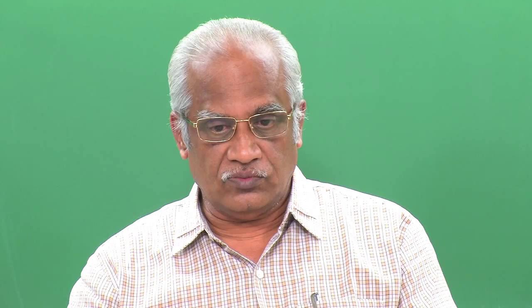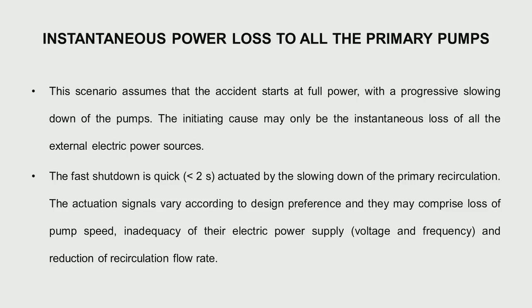Another scenario: there is an instantaneous power loss to all primary pumps. The primary pumps receive no power. They have some inertia in their drive system, so they slow down gradually, but the power is gone. This is an unsafe situation, so we trip the reactor in less than 2 seconds. The flow reduction also gives a signal, and loss of voltage at the pump — many signals together ensure a shutdown of the reactor.